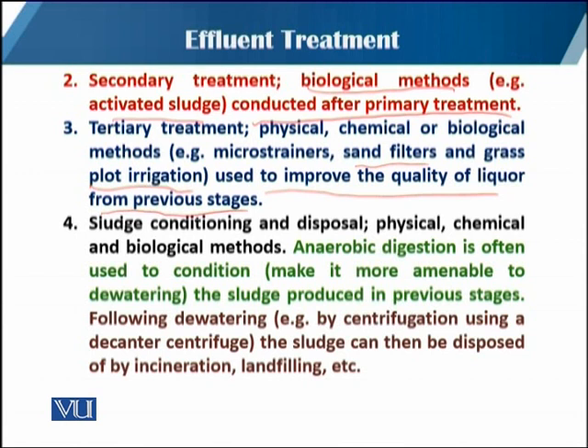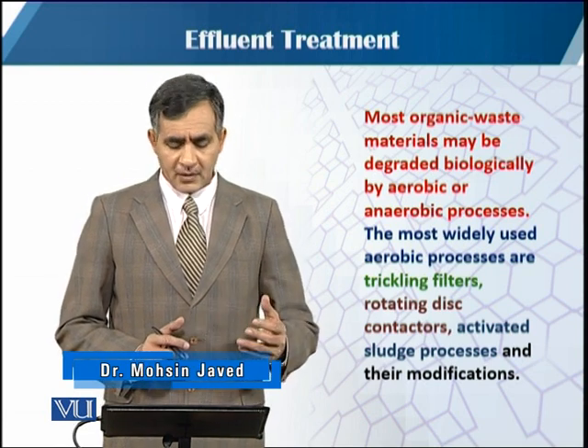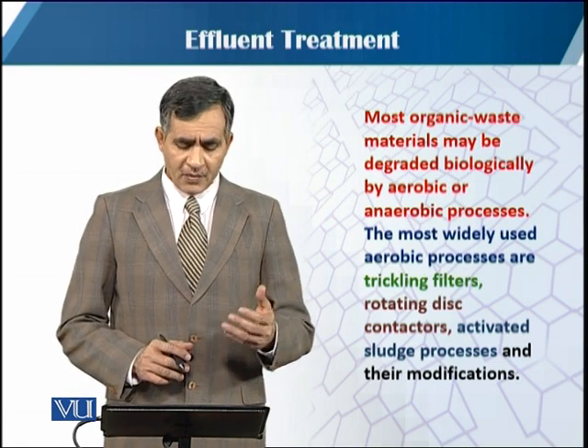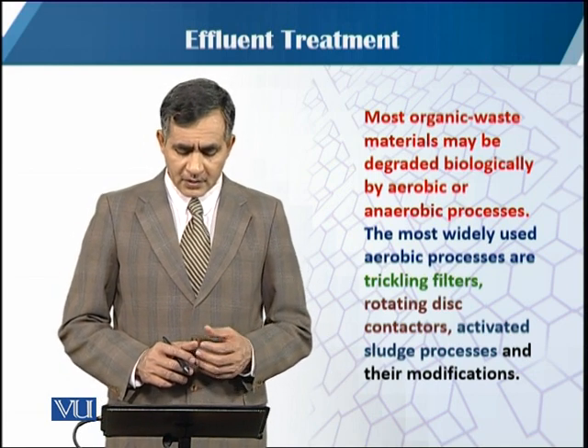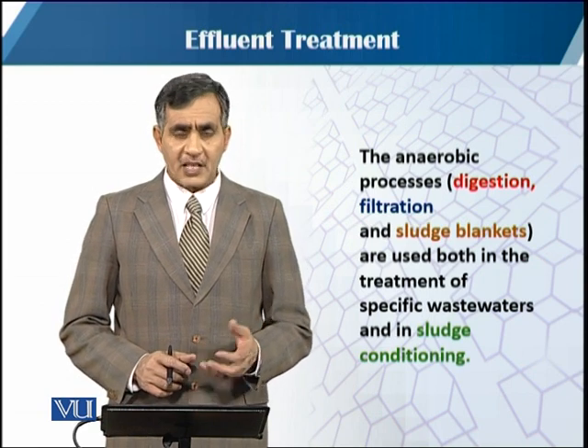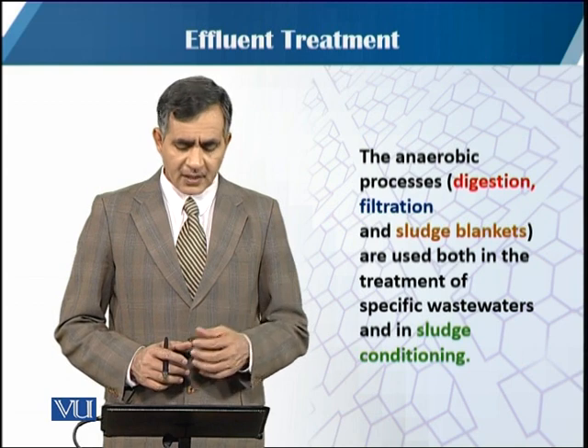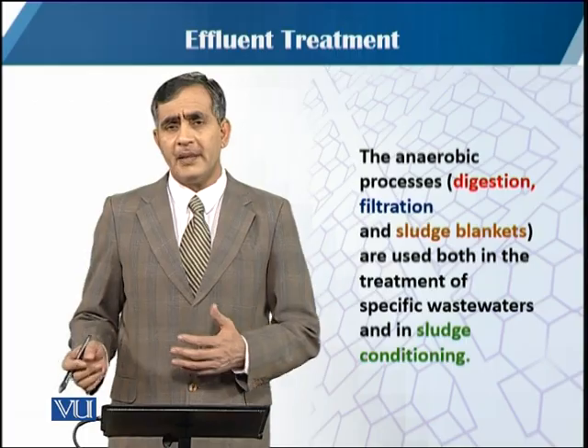The fourth stage is sludge conditioning and disposal, using physical, chemical, and biological methods in which anaerobic digestion is often used for conditioning, followed by dewatering using centrifugation with decanter centrifuges. The sludge can then be disposed of by incineration or landfilling. Most organic waste material may be degraded biologically by aerobic or anaerobic processes using different organisms. The most widely used aerobic processes are trickling filters, rotating disc contactors, and the activated sludge process. Anaerobic processes include digestion filters and sludge blankets, used both in the treatment of specific wastewater and in sludge conditioning, sometimes combining both aerobic and anaerobic strategies.